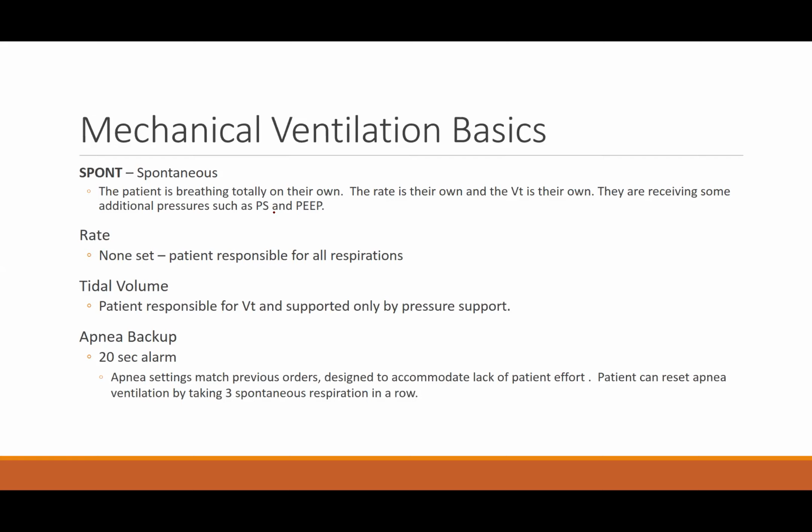I actually don't like that definition very much because on a spontaneous setting, let's go back a couple slides where we talked about positive and negative pressure ventilation. What the ventilator reads is that the patient is trying to initiate a breath. It reads that negative pressure of the patient trying and starting to inhale, and then the ventilator kicks in and gives that patient just a little bit of help to really assist in getting those lungs inflated, okay?